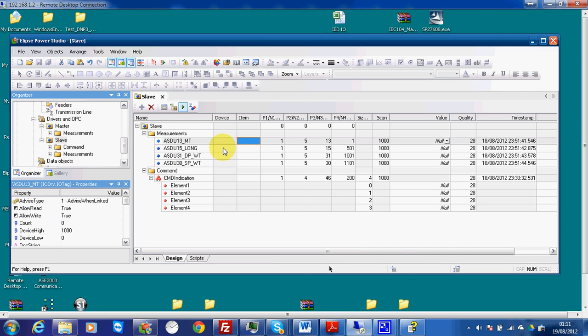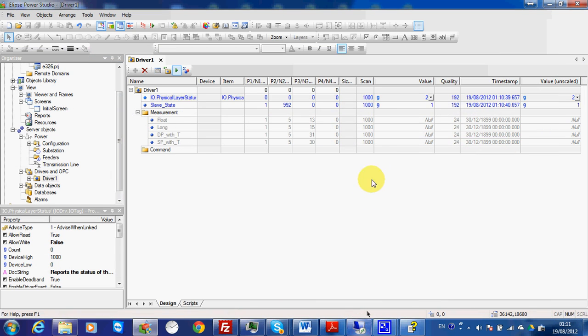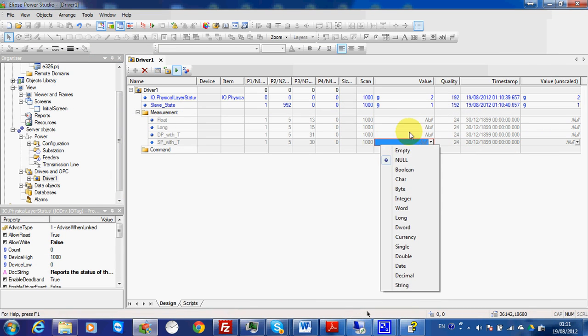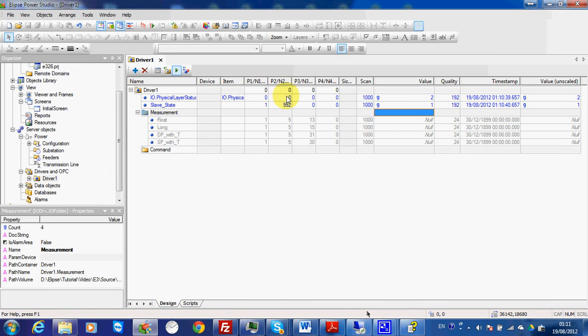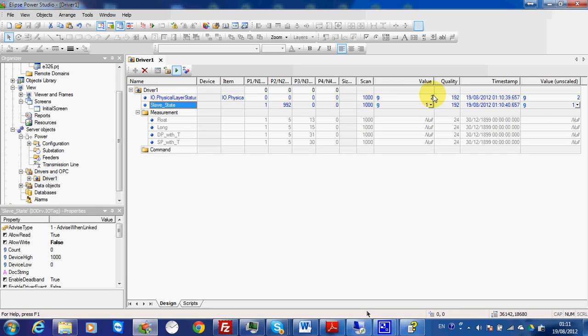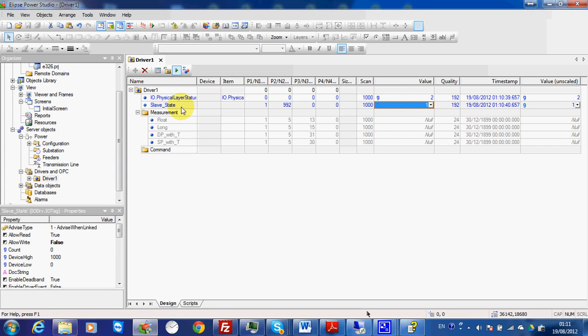After some time, the communication is now okay. The physical layer shows 2, which means communication is established. The slave state tag, which is a specific tag for IEC 104, also confirms the communication is now okay.